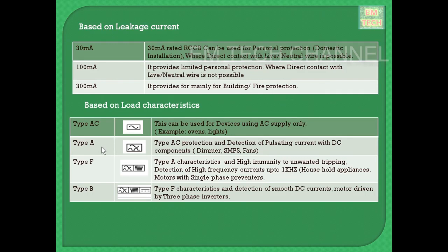The type AC RCCB can be used where the devices are fed with AC supply, for example ovens and lights. Type A RCCB combines the function of type AC RCCB and additionally it can detect pulsating currents with DC components. Examples of devices where it can be used are dimmers, SMPS, fans, etc. If you look at the type A RCCB symbol, you can see that it combines the type AC RCCB symbol also.